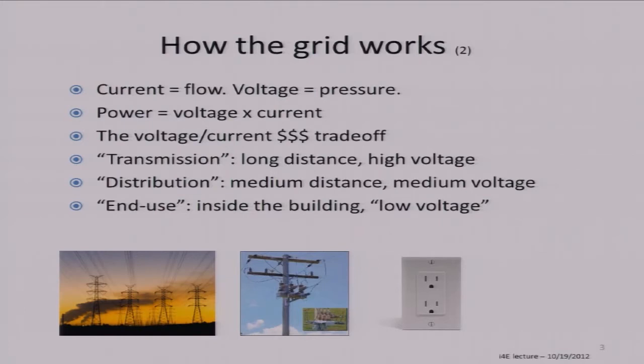It turns out that all the losses in power distribution systems come from the current, not the voltage. The more current you push, the more losses you have, and it's more or less related to the square of the current, so it's really sensitive to how much current you're trying to move through the system. Consequently, to move a given amount of power, you want to do it at the highest possible voltage you can get away with, to have the lowest possible losses.